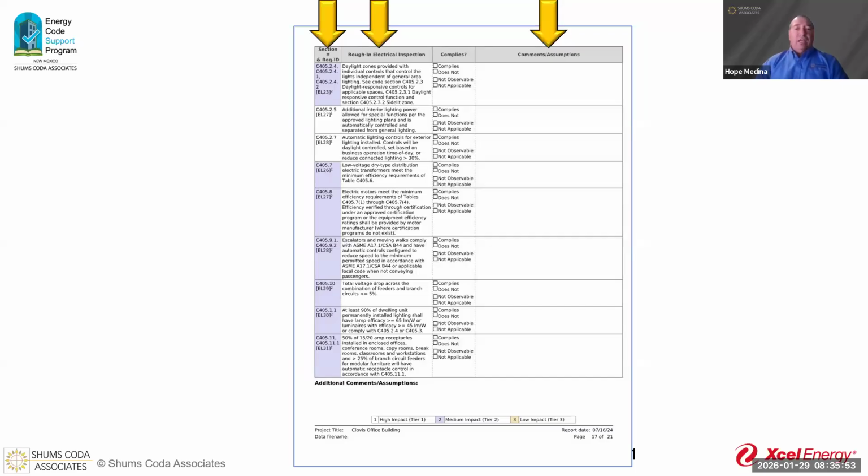And then I would request a plan revision so we know that they're correct and we have accurate documents. Some folks will be able to redline those plans, just write in the field that, hey, per the checklist, this time control was installed here and good to go that way. So there's a couple different ways of handling that.